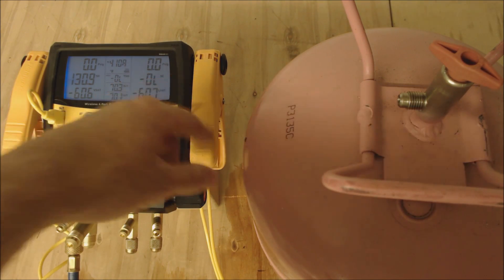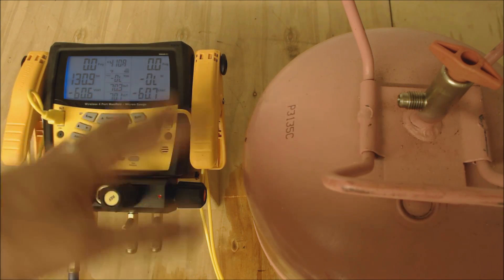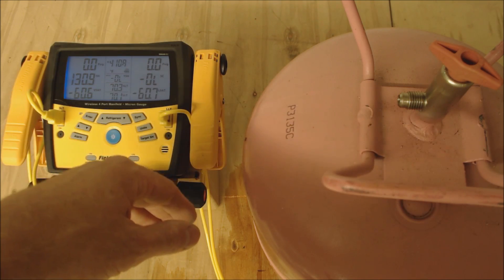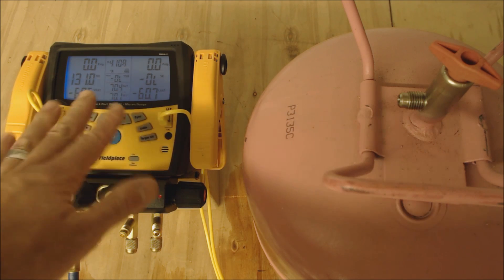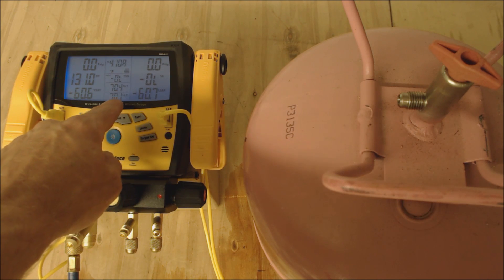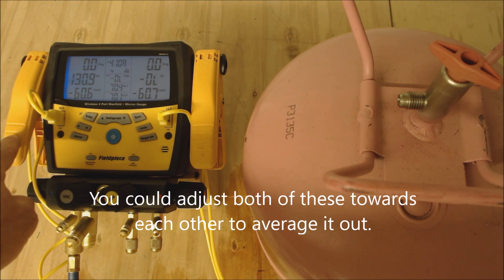Just so you know, I dried these temp clamps off and let them absorb the temperature in the room. It took quite a bit of time, but now they're 0.2 to 0.3 degrees off from each other. It says 70.2 on the liquid line temperature and 70.4 on the suction line temperature.